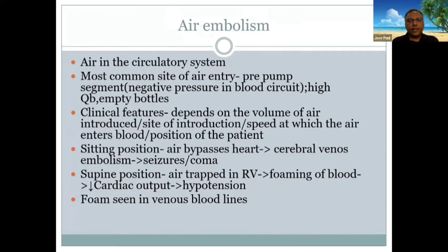Now coming to technical complications, air embolism. This is again a very dramatic acute complication of hemodialysis. It is due to the presence of air in the circulatory system. The most common site of air entry is the pre-pump segment. In the pre-pump segment, there'll be negative pressure in the blood circuit, and often there is a high blood flow rate. The usual cause is an empty bottle which is connected to the negative pressure pre-pump segment of the blood circuit.